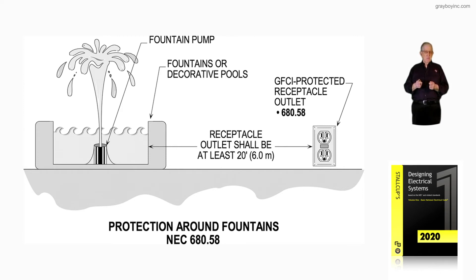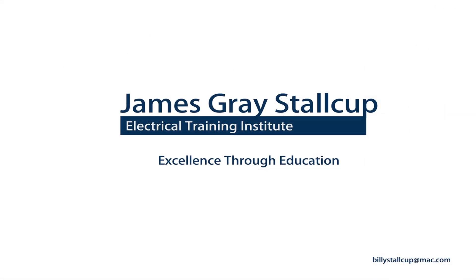Notice GFCI protection for that receptacle would be required by NEC 680.58 where you had a fountain motor pump spraying the water up and forming an up-and-down water type configuration. Figure 10-32B illustrates where that receptacle, in accordance with the 2020 NEC, must be located — now clearly a 20-foot rule outlined in NEC 680.58.